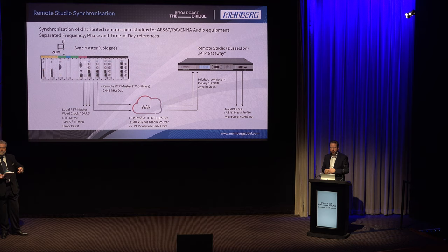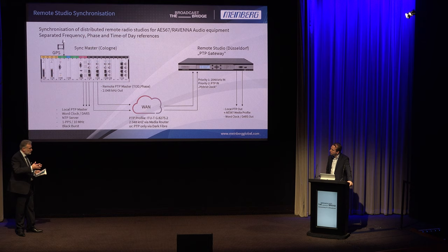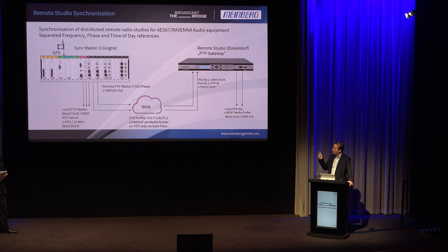Okay, thank you. I think it's just one last question over here. Is it fair to say, Daniel, that we also have to be concerned with the number of devices connected to a clock? Because if we have too many devices and there are too many message requests, then that can also impact time accuracy. No, the accuracy should not be an issue here. It's just a point where the packets seem to start to drop. And you only have this problem in networks where you use transparent clocks or no PTP-aware switches.